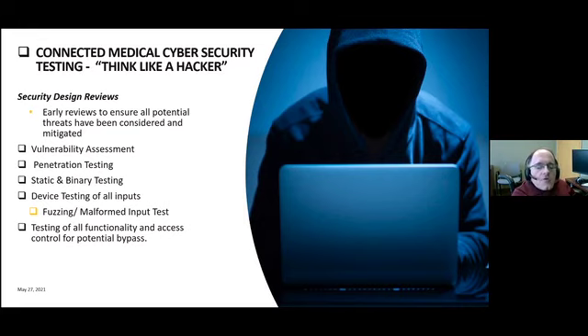You also, for a lot of these standards, are going to start to see that we're looking at static and binary code testing. So we're going to be looking at getting your software tested to make sure that it's not vulnerable. These standards for medical devices really stress that requirement, and it's critically important. The thing is malformed input, and this has been a big thing for the FDA and a number of clients. We're even getting requests from medical associations in Japan and around the world saying, we have devices that have USB ports and other things. We want to have them fuzzed. We want to have them manipulated. We want to make sure that the device will respond to bad attacks.